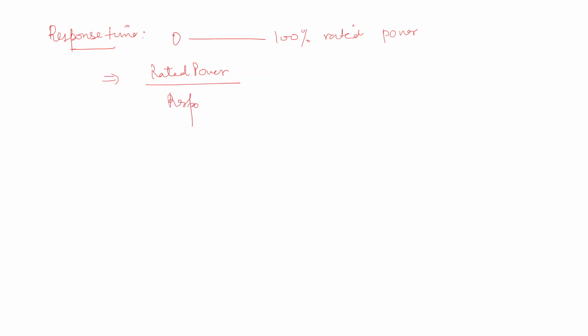The next term here is response time. What is response time? It is described as the time for an ESS to go from 0 to 100% of rated power. And if we divide the rated power by the response time, what we get is the ramp rate. These are some of the terms we use when we calculate anything about batteries.